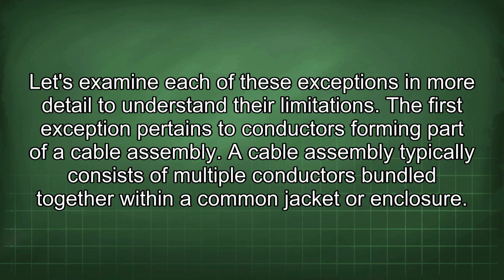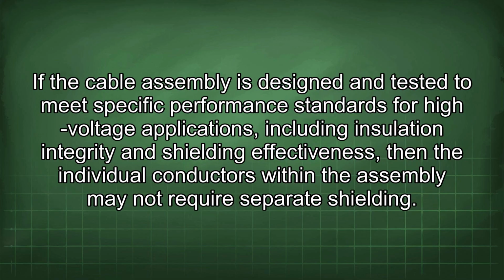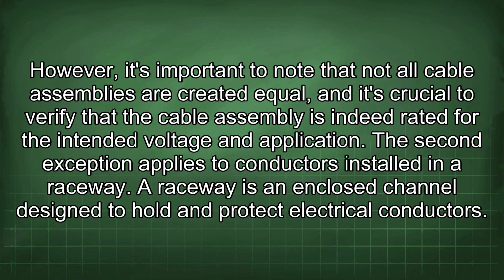A cable assembly typically consists of multiple conductors bundled together within a common jacket or enclosure. If the cable assembly is designed and tested to meet specific performance standards for high-voltage applications, including insulation integrity and shielding effectiveness, then the individual conductors within the assembly may not require separate shielding. However, it's important to note that not all cable assemblies are created equal, and it's crucial to verify that the cable assembly is indeed rated for the intended voltage and application.